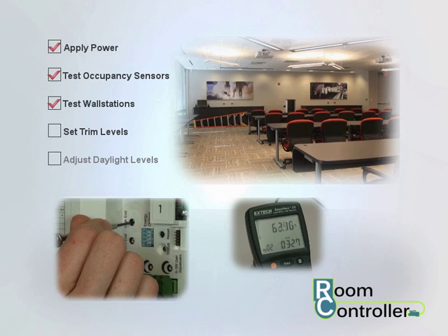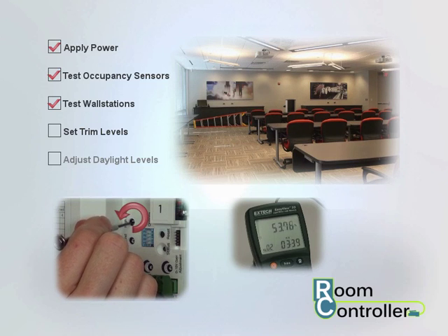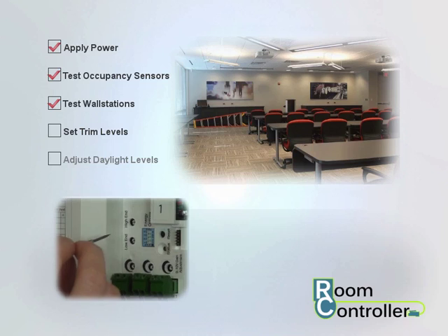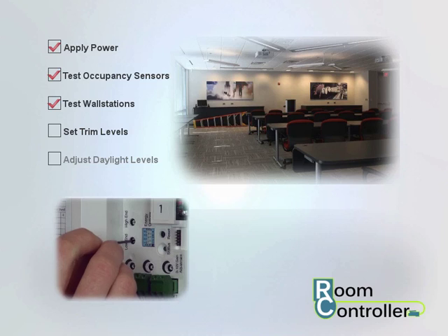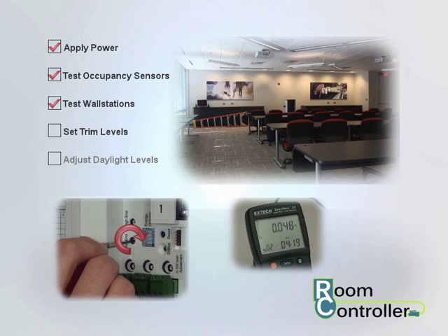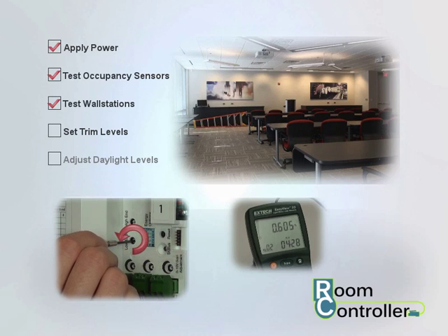Turn the dial counter-clockwise in small increments until the light level is at the desired maximum. Next, turn the minimum trim dial clockwise and then fully counter-clockwise. The light level in the room will go to full dim. Turn the dial clockwise in small increments until you begin to notice the light level increasing in the monitored space, then turn the dial slightly counter-clockwise from where this change begins.